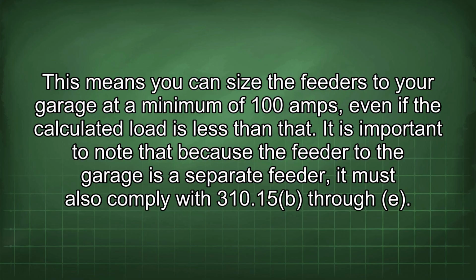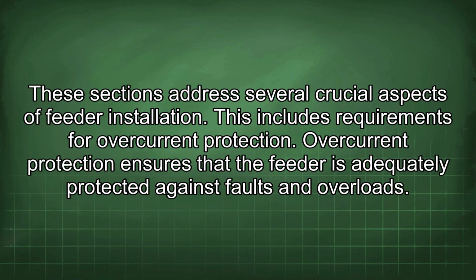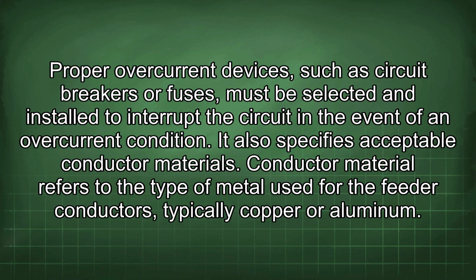It is important to note that because the feeder to the garage is a separate feeder, it must also comply with 310.15(b) through (e). These sections address several crucial aspects of feeder installation. This includes requirements for overcurrent protection. Overcurrent protection ensures that the feeder is adequately protected against faults and overloads. Proper overcurrent devices, such as circuit breakers or fuses, must be selected and installed to interrupt the circuit in the event of an overcurrent condition.